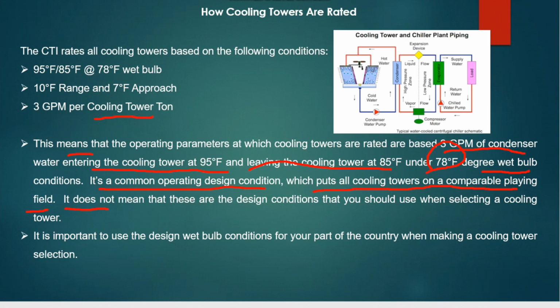So it doesn't mean that, for example, if you are in the UAE, where as per the Dubai Municipality Dubai Green Building Code you have to consider a 46 degree dry bulb and 29 degree wet bulb condition, you can ask, the wet bulb I am using for my region is different. So here is the point. It doesn't mean that these are the design conditions that you should use when selecting a cooling tower. They are very clearly saying that. This is not the design condition you should use for your cooling tower. It is important to use the design wet bulb condition for your part of the country when making a cooling tower selection. Based on your country or your region, you have to select the cooling tower considering the local wet bulb temperature. So the value which they rated here is the rated condition, and as they mentioned clearly here, this is the common operating design condition to compare on a level playing field.